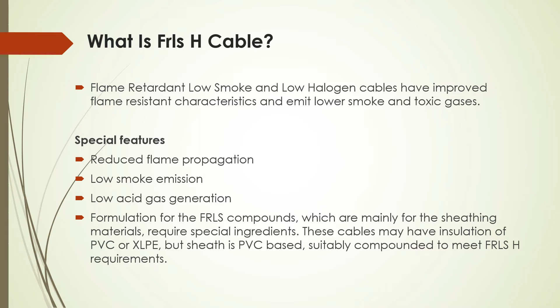Formulation for the FRLS compounds, which are mainly for the sheathing material, requires special ingredients. These cables may have insulation of PVC or XLPE, but the sheath is PVC based, suitably compounded to meet FRLS requirements.